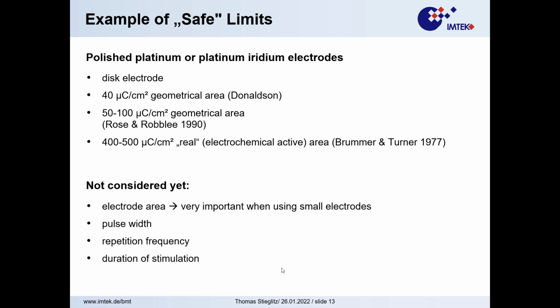So if you would ask Nick Donaldson, he would say 40 microcoulombs per square centimeter geometrical area is the safety limit. If you go on, Timothy Rose and Lois Robblee have passed away, so you cannot ask them any longer. They have reported in their publications it's between 50 and 100 microcoulombs per square centimeter geometrical area, which is close to 40, so we're still in the same order of magnitude. But you find others, Brummer and Turner, and they said we take 400 to 500 microcoulombs per square centimeter. That's a factor of 10.